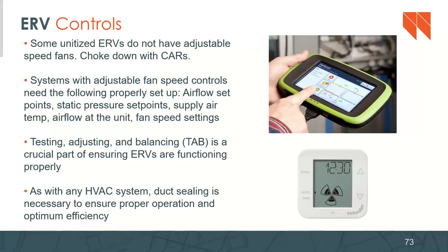All right, so we talked about controls being a concern on some of these larger systems. So, considerations for controls for unitized systems: sometimes they don't have adjustable speed on the actual fans themselves, and so you have to damper them down with a damper like a CAR damper. Systems with adjustable fan speed controls have to be set up properly. And of course, testing, adjusting, and balancing is always a crucial part of any system, especially ventilation systems. And duct sealing has got to happen in order to get to the flow rates that you're hoping for and that the system has been designed to.